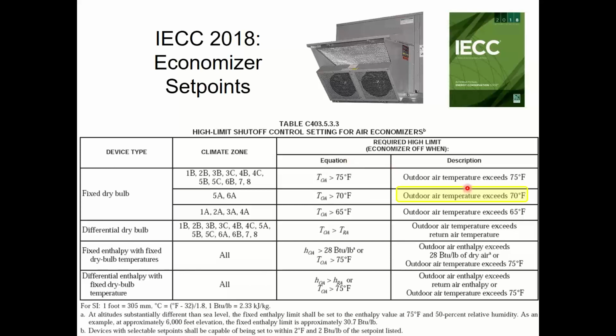Well, now the code says at 70. I know that between 62 and 70, I'm going to have complaints. I've had enough jobs to know. But that's the law. That's what I've got to set it for. Technically, I could set it for 68 because if you look down here, it allows you to have a 2-degree span. So 70 is defined as anything between 68 and 72. That would be compliant. If I want to do an enthalpy economizer, then it goes from 70 to 75, meaning I've got to take air on a 73 or 74 degree day. But I also get to babysit the enthalpy, i.e. the humidity. And if it's 28 BTUs per pound, then I don't have to do it. There's a plus or minus 2 on that too.